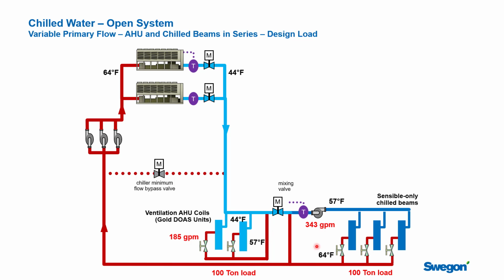So now what happens? What happens here is that at this point in the pipe, we have 185 GPM. It's got to go somewhere, so it's going to continue along this line. But we're actually going to add another 55 GPM to it, so that when we get to here, it's 240 GPM, right? 185 plus 55 is 240. This 55 GPM water is at 44 degrees, so it's going to cool the temperature down a little bit, from 57 to a little bit less. And when we do that, we will need some return water here because we've got to get all the way up to 343 GPM. And we need a little bit of heat to offset this cooler water that's coming in because we want 57 degrees.